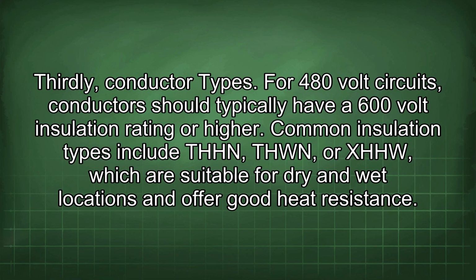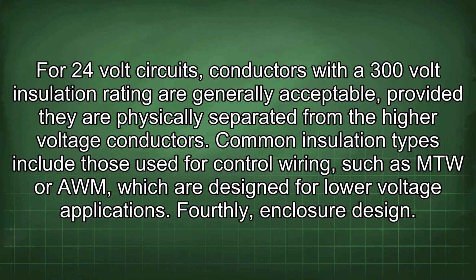Thirdly, conductor types. For 480-volt circuits, conductors should typically have a 600-volt insulation rating or higher. Common insulation types include THHN, THWN, or XHHW, which are suitable for dry and wet locations and offer good heat resistance. For 24-volt circuits, conductors with a 300-volt insulation rating are generally acceptable, provided they are physically separated from the higher voltage conductors. Common insulation types include those used for control wiring, such as MTW or AWM, which are designed for lower voltage applications. Fourthly, enclosure design.